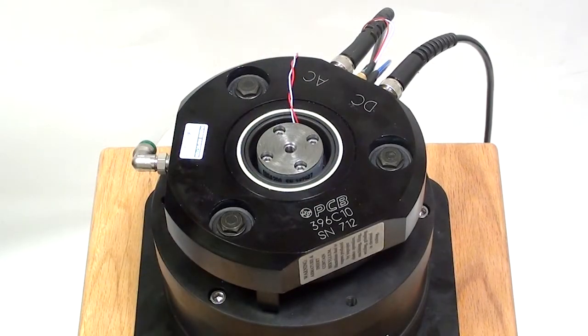Never scrape, abrade, grind, or lap the mounting surface of your calibration shaker.